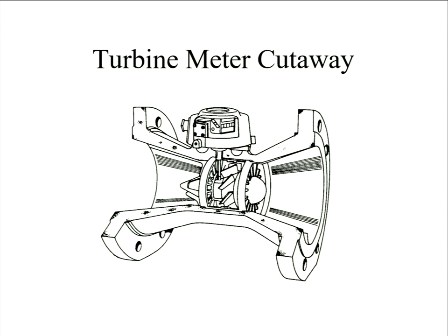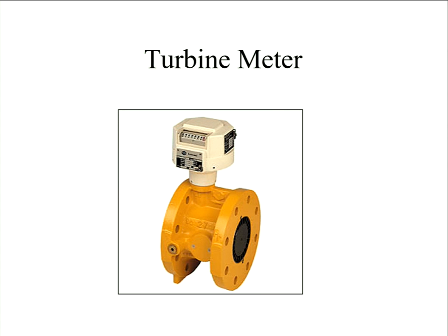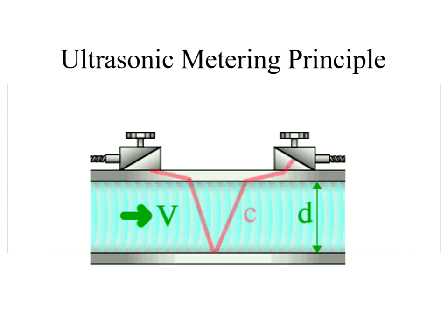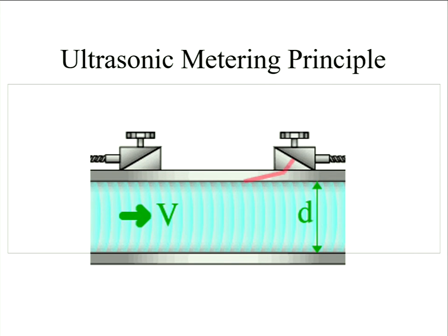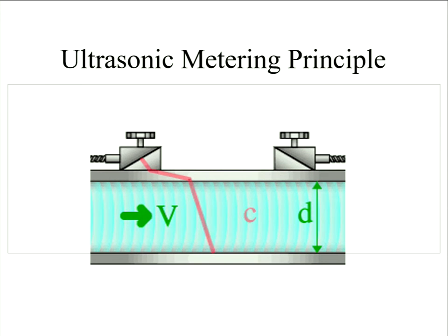The trouble is, the electronics are considerably more complicated because you've got a number of heads. But if you've got heads all the way around, usually you've got a deal of resilience, and again, a lot of the modern ones will come with condition monitoring software, so you can start to see if you're losing signals somewhere. It doesn't have problems with contamination like an orifice plate. Turbine meters are even worse. If something hits a blade on a turbine meter, it can damage it, and it's also very difficult to get out.